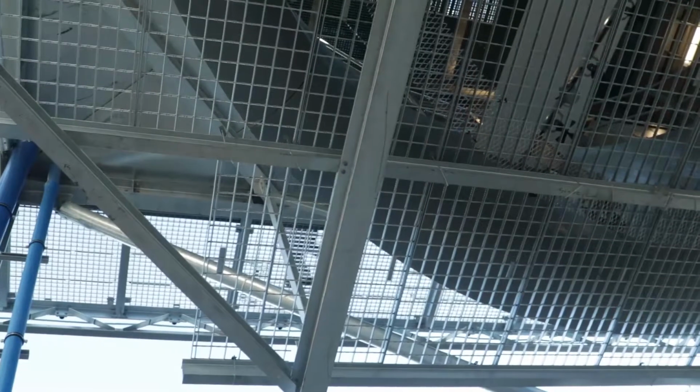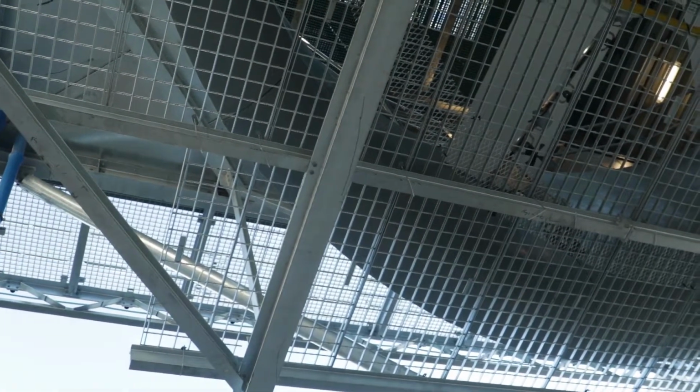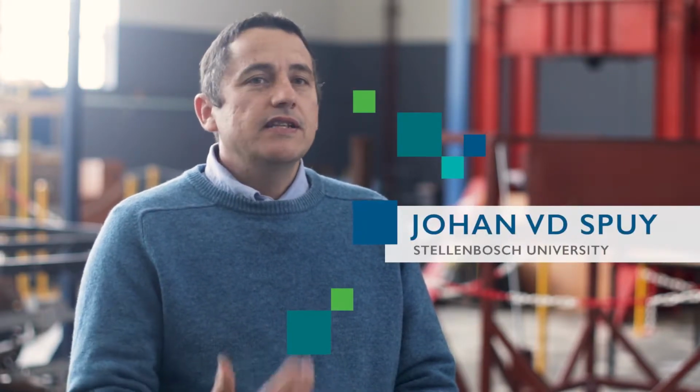The new system integrates the wet part directly into the dry part. So we don't need the surface condenser, the water circulating system, as well as the wet cooling towers. You can integrate it directly into your conventional air-cooled condenser system, by replacing one of the air-cooled condenser cells with this deluge condenser. Then there's a second technology where we develop axial flow fans to improve the fan static efficiency. Stellenbosch University specifically was chosen because we have extensive experience in cooling system design and analysis.